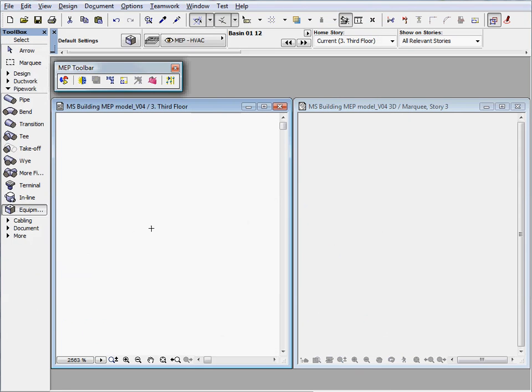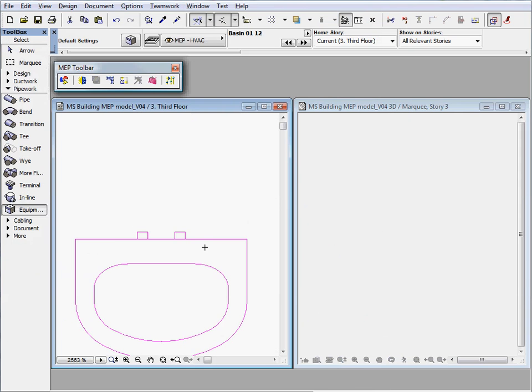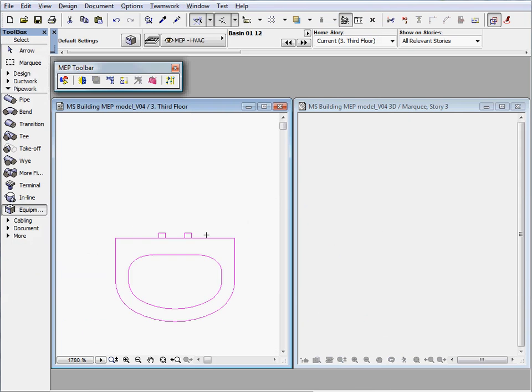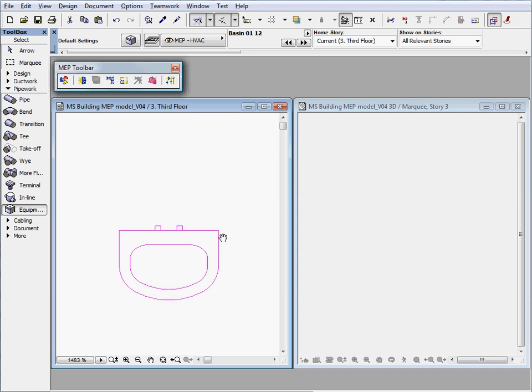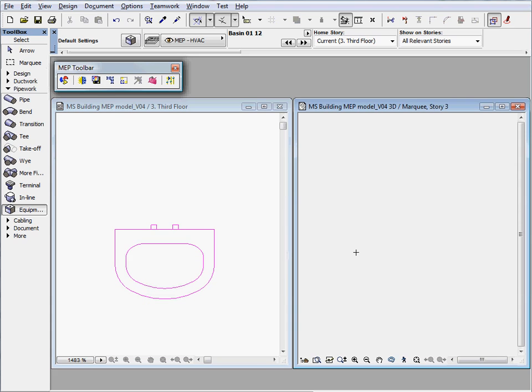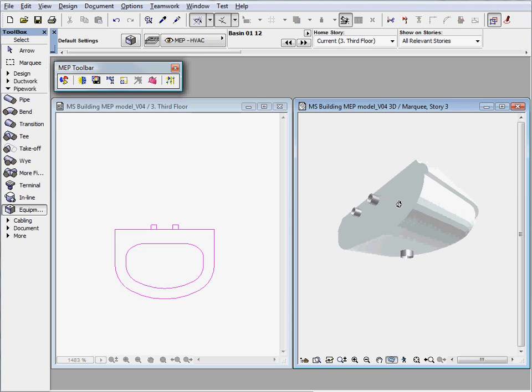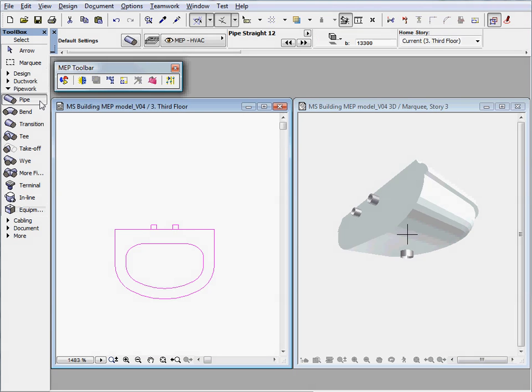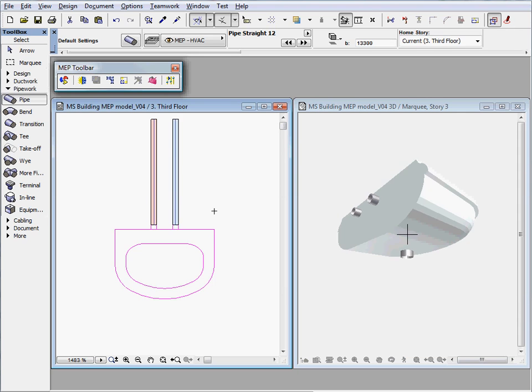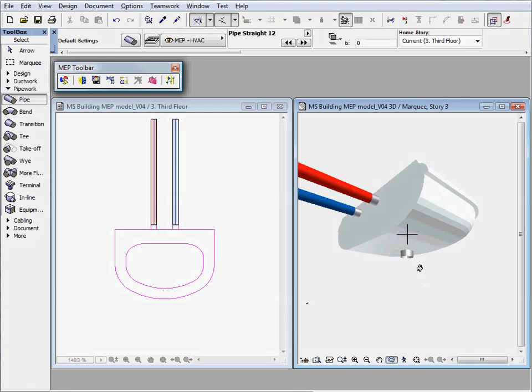Let's see how this works in practice and place a basin on the floor plan view. Notice that the water connections are clearly visible on the floor plan and also in the 3D view. Let's activate the pipe tool and click the hot and cold water connections on the floor plan. Notice that the diameter and the color of the pipes are automatically adjusted to fulfill the previously defined basin connection settings.